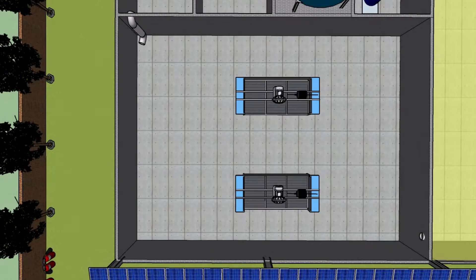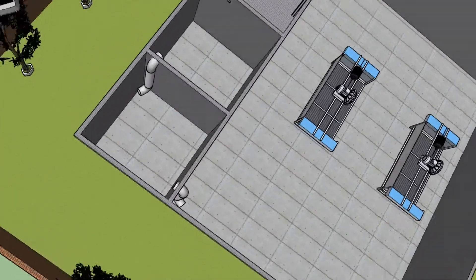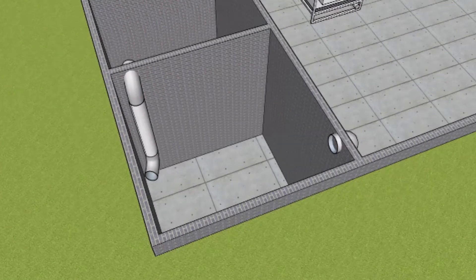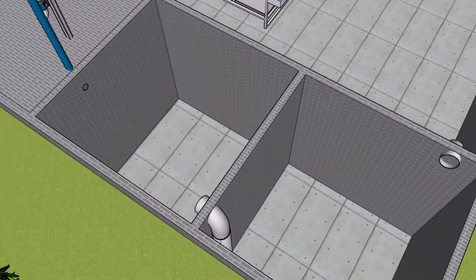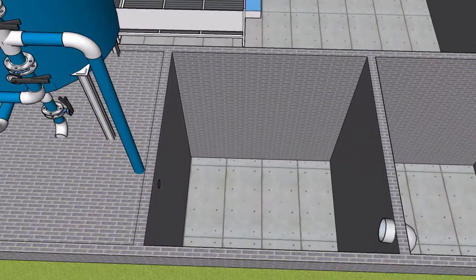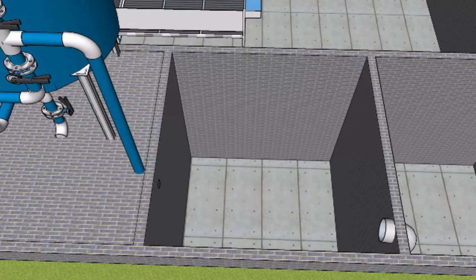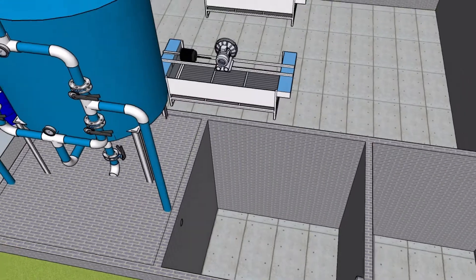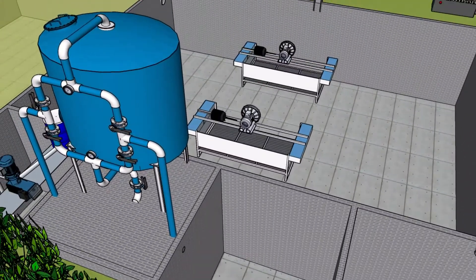The settling tank has a tube settler which helps in reducing the suspended solids available in the treatment. In the phosphorus removal tank, iron media is introduced and phosphorus is attracted by the iron media and taken out periodically.